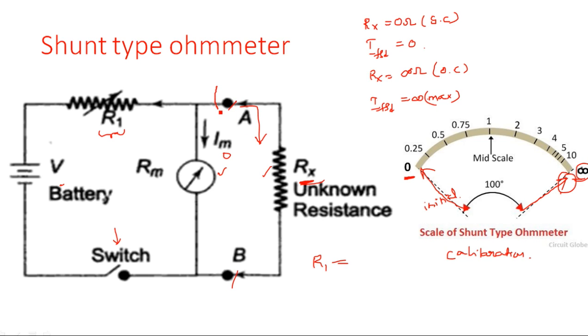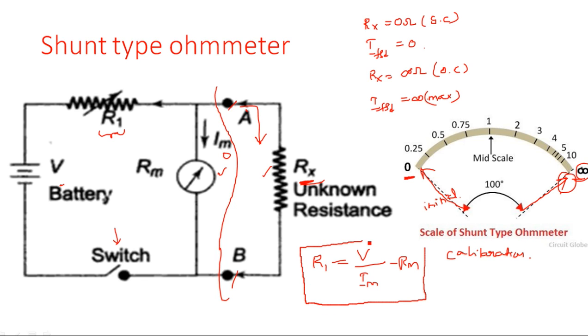If you eliminate the part between A and B, the circuit simply appears like a voltmeter — a multiplier resistor R1 in series with the meter. In that case, what is the formula for the resistor? It is V divided by Im minus Rm. There is no need to do a lot of calculations for the shunt type ohmmeter like in the series type. Here we have only one resistor, and when you eliminate the unknown resistor Rx, it simply appears like a normal DC voltmeter. Calibration is also in the conventional way from left to right.